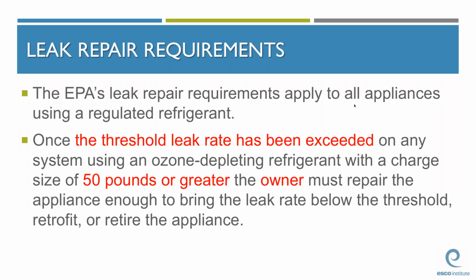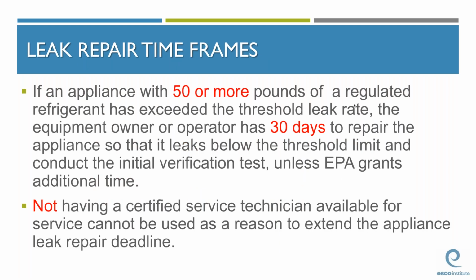These leak rate and leak repair requirements are the same for Type 2 and Type 3, so you'll be hearing more about this during next week's webinar. So once it's been determined that an appliance has exceeded the threshold leak rate, the equipment owner or operator has 30 days to repair the appliance so that the leak rate is below the threshold limit. At this time, an initial verification leak test must be performed. Once again, this rule applies to systems with a total refrigerant charge of 50 pounds or more.